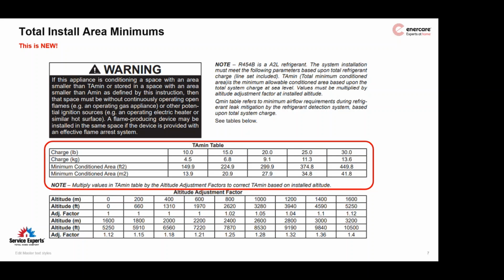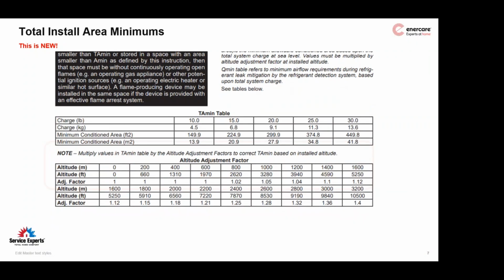The warning on the top left also states that there cannot be an open flame appliance without an effective flame arrest system. Any gas appliances like furnaces and gas-fired water heaters within that same space will both need to be considered. We're going to get into a little more detail as we move forward, but I want to go through an example, sizing the room first, to give you guys a sense. So you guys can open up your mics here because you're going to see what's coming.